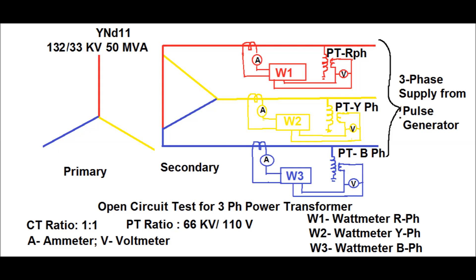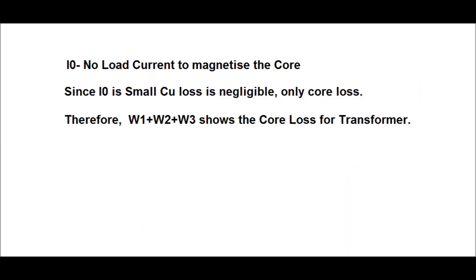Since the primary is open-circuited, the current taken from the LV side is very minimal — this is called the no-load current, which magnetizes the core. Because the no-load current is very small, copper losses will be negligible; the main loss is the iron loss. In the open circuit test, since the high voltage side is kept open, the no-load current I₀ — which is the magnetizing current — flows in the LV side. Therefore, the summation of W1, W2, and W3 gives the core loss or iron loss of the power transformer.